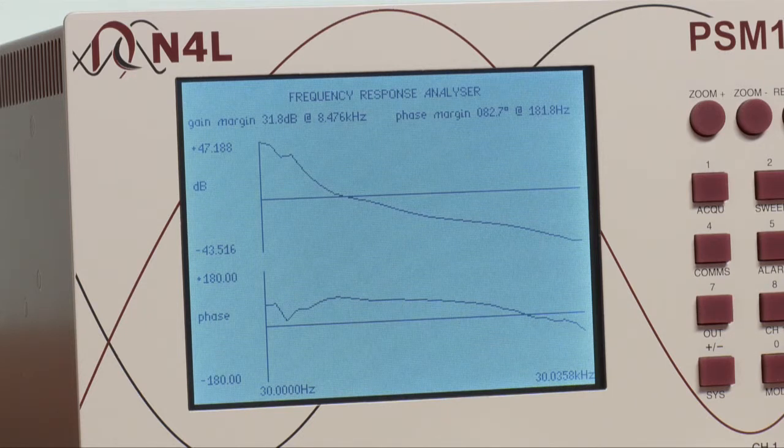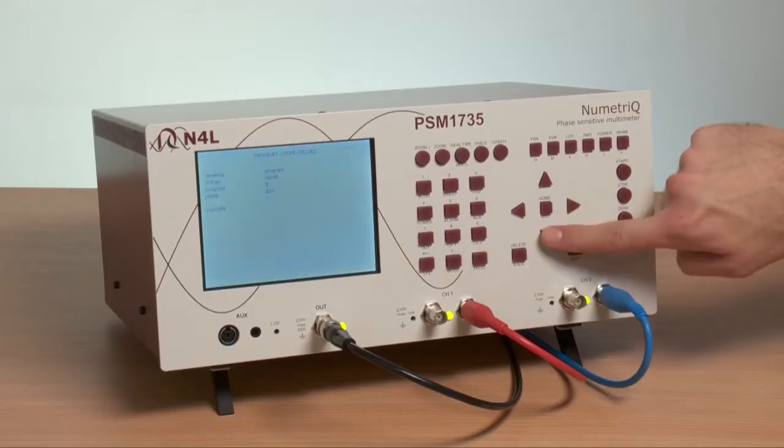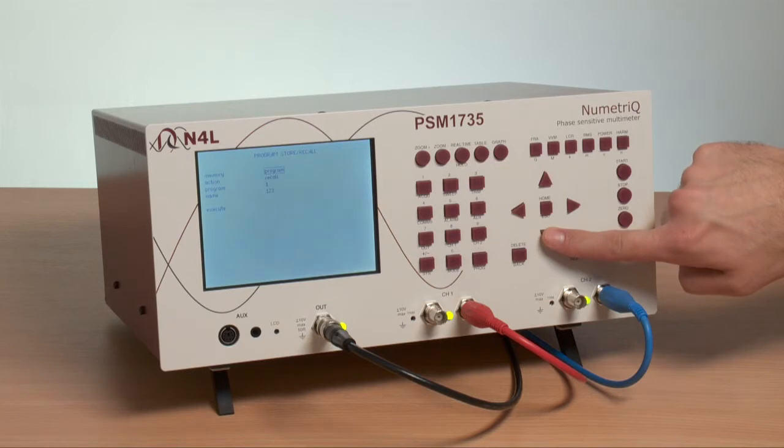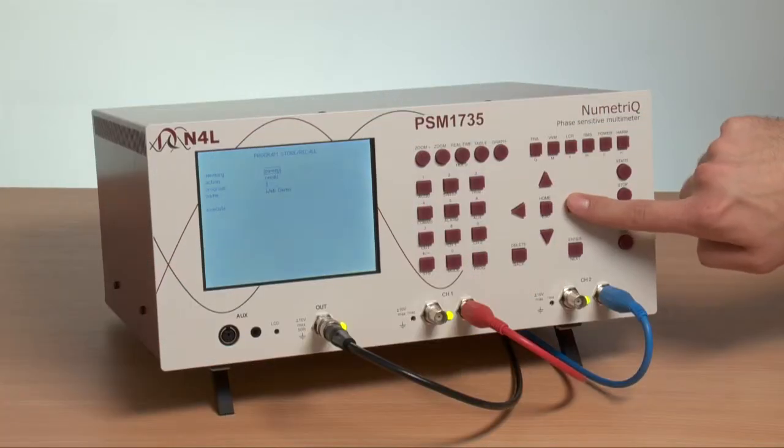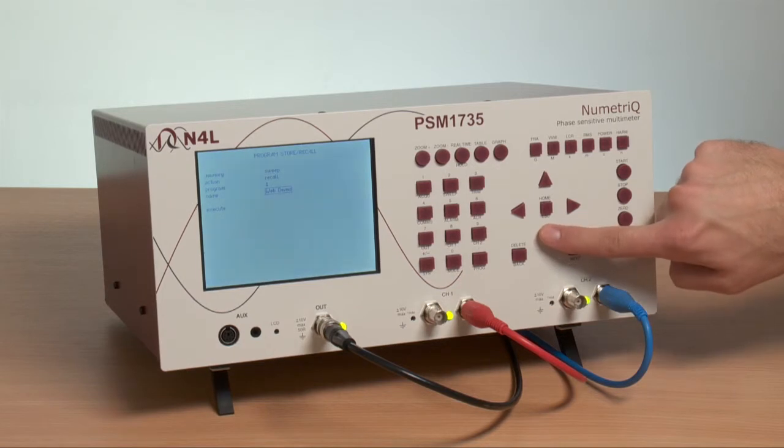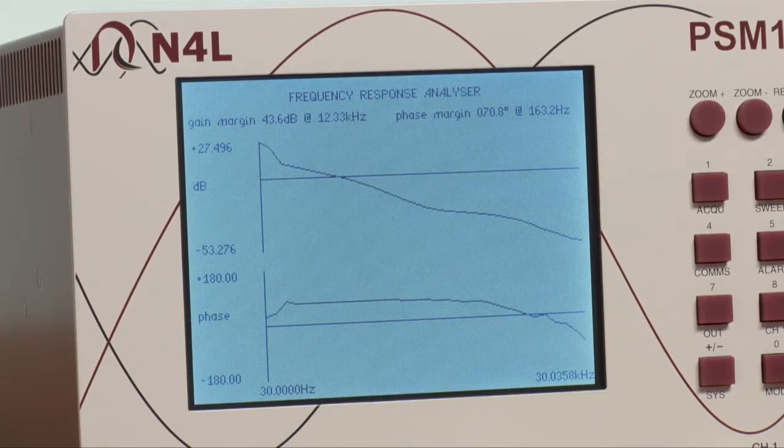We have in the internal memory a previous sweep measurement saved. To illustrate this, if we go into the program menu, we can recall programs, data logs, or sweeps. And if we recall a sweep we have made recently and select Execute, you can see that the program is loaded. And that can be compared to other plots or exported to a PC.